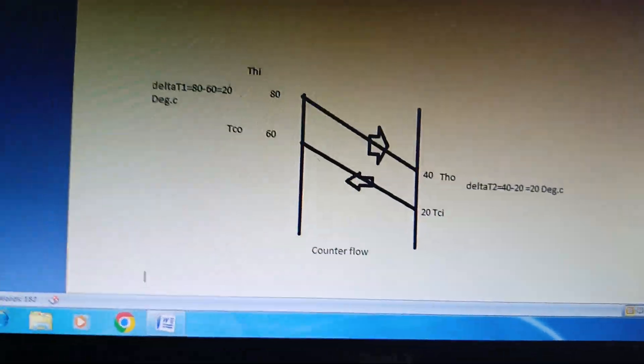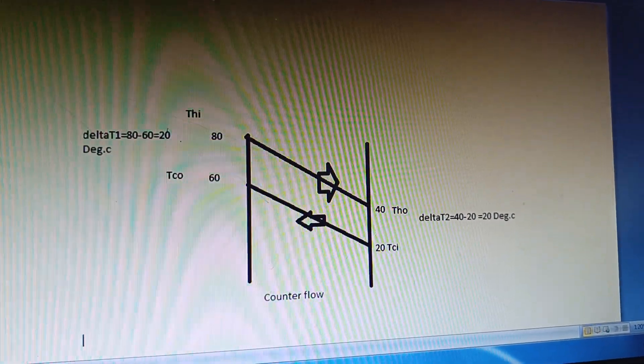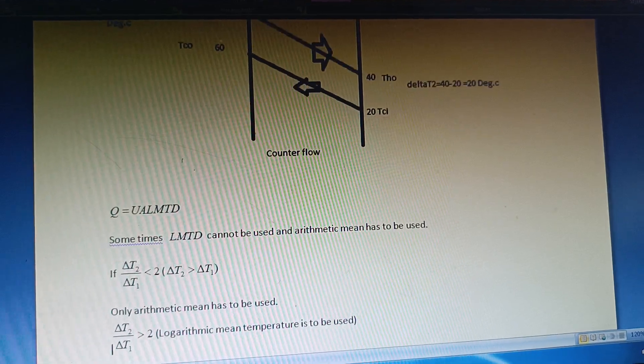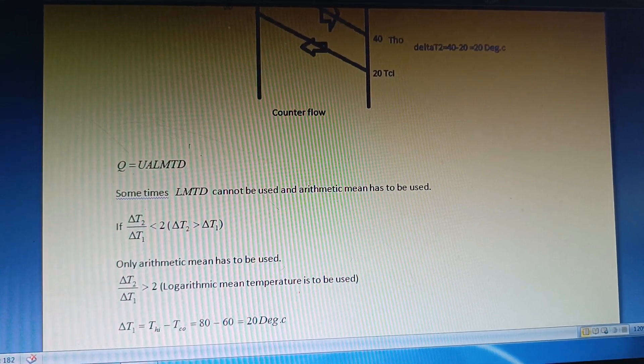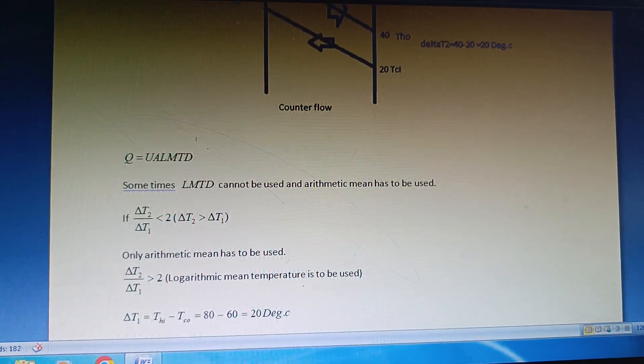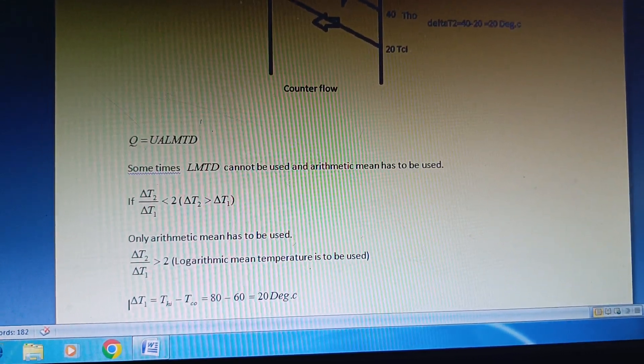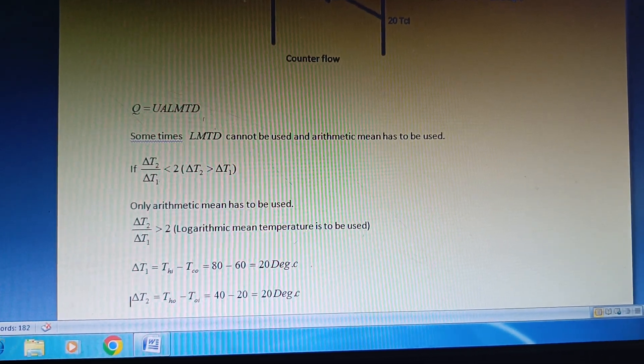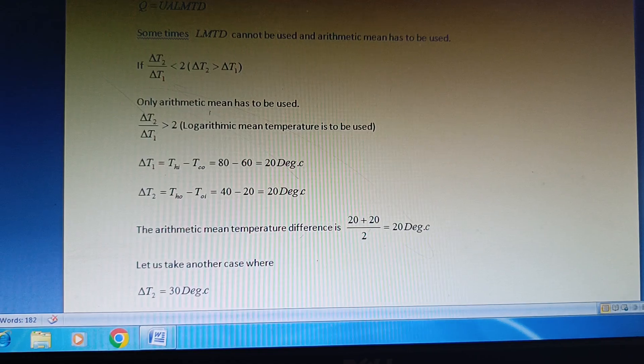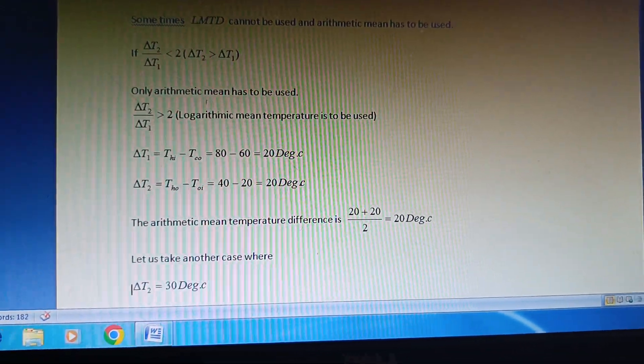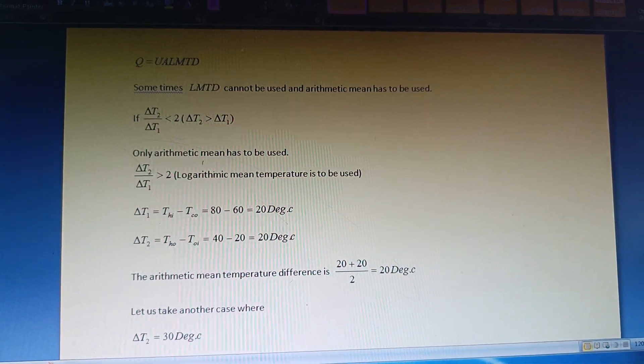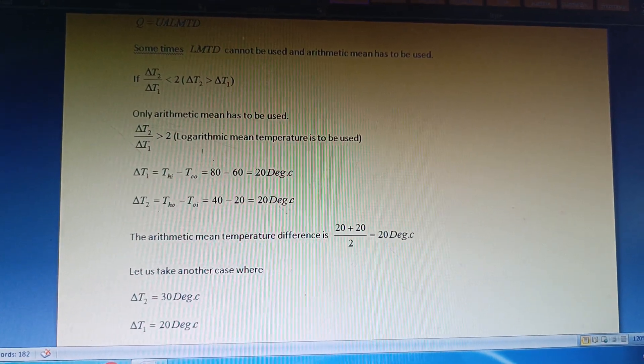So how do you decide which mean to use? The rule is: with the condition that ΔT2 > ΔT1, if ΔT2/ΔT1 is less than 2, use arithmetic mean temperature difference; if ΔT2/ΔT1 is greater than 2, use logarithmic mean temperature difference. In this case, ΔT2/ΔT1 = 20/20 = 1, which is less than 2, so we must use arithmetic mean temperature difference: (ΔT1 + ΔT2) / 2 = 20°C.